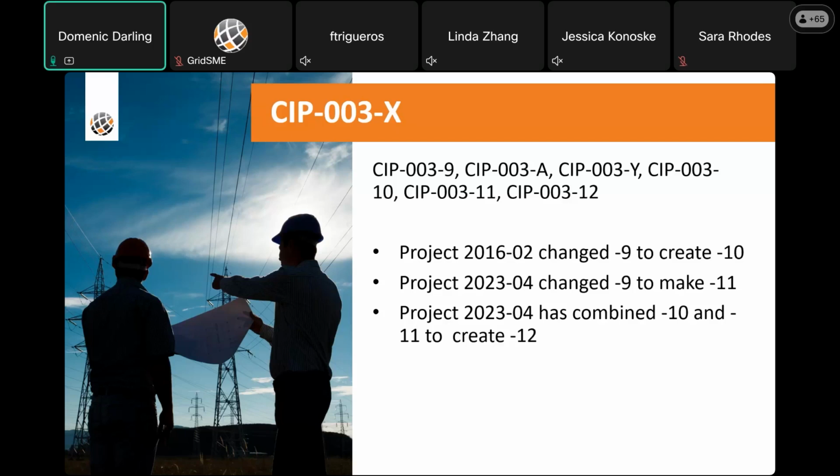It was rooted again in those concerns around the development of CIP 013, which only applies to medium and high impact BES cyber systems. NERC and additional staff throughout the ERO wanted these supply chain management requirements extended to low impact systems, especially around remote vendor access. And that's where we got CIP 003-9 in response to that, approved by FERC in 2023. It has an enforcement date of April 1st, 2026, and includes that new Section 6 we had on the last slide, which requires entities to determine, disable, and detect remote access communications.